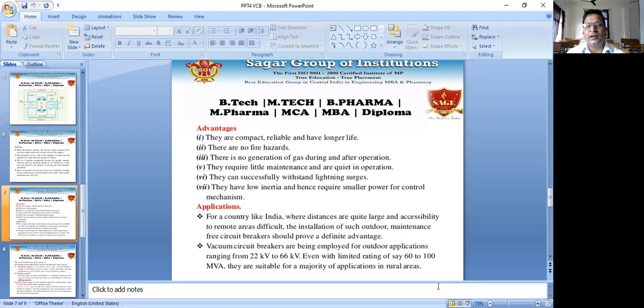For a country like India, where distances are quite large and accessibility to remote areas is difficult, the installation of such outdoor maintenance-free circuit breakers should prove a definite advantage. Vacuum circuit breakers are being employed in outdoor applications, with ratings from 22 kilovolt to 66 kilovolt, even with a limited range of, say, 60 to 100 megavolt ampere. They are suitable for the majority of applications in rural areas.